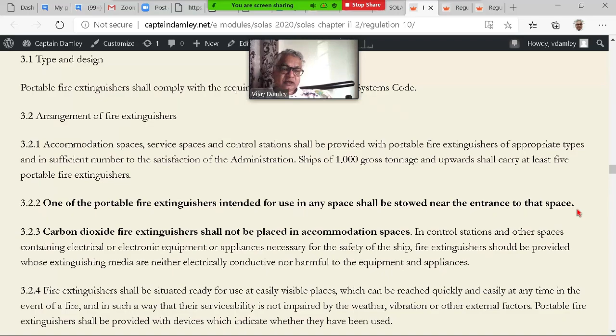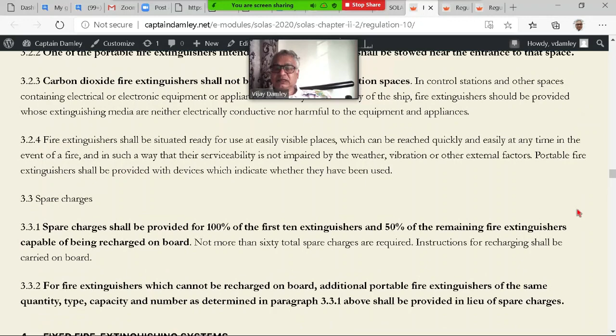Then carbon dioxide extinguishers are not placed in accommodation spaces because of toxicity, except in galley. Galley has got arrangement where we use this. Another important part, spare charges must be approved type. Then 100% for first 10 extinguishers, 50% for remaining. Now this condition, spare charges must be there at the time of departure from any port. Not that every 3 months and 6 months, no, from any port.